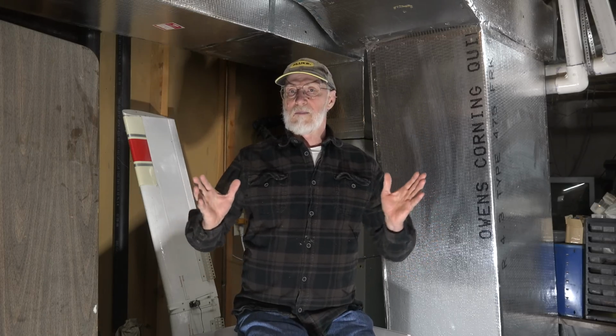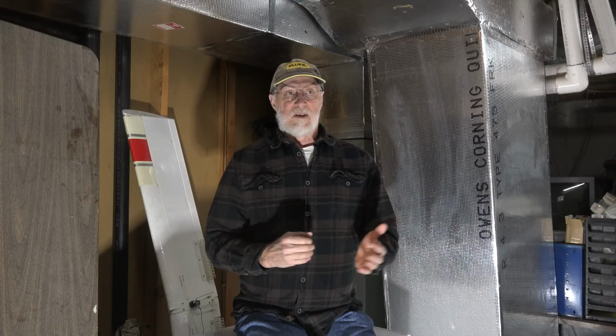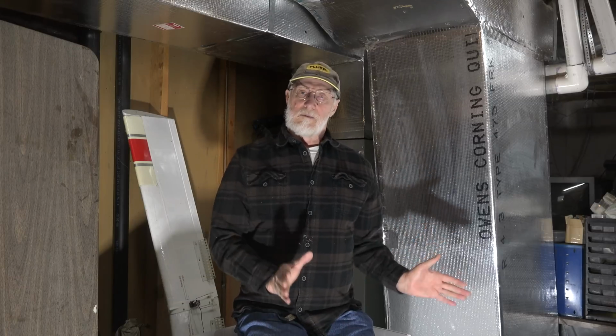In this series on ductwork, I've tried to give you some tools on how to find problems with ductwork, failures that are common, pressure drop across components, you know, coils, filters. Filters are a big problem. Even clean filters, if they're the wrong type, are a problem. But I've tried to give you some tools to look at these things and find out where the problem is and what it should look like.